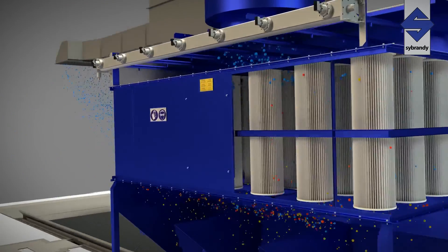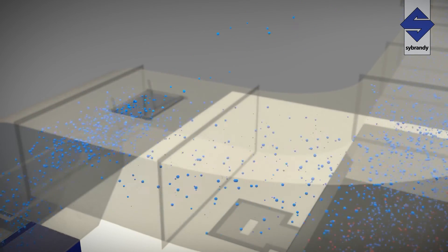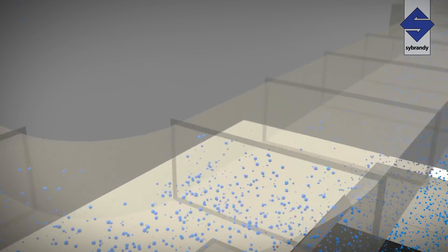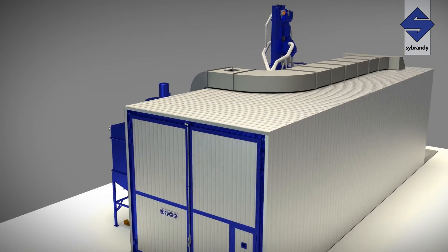The clean air is directed up and into the ducting. A percentage of the cleaned air is vented to atmosphere to create an under pressure environment, with the remainder being returned into the blast room where the cycle begins again.